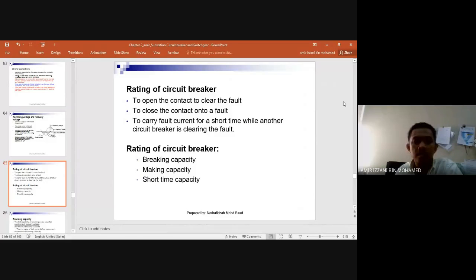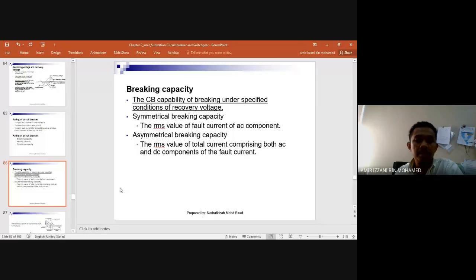Rating of circuit breaker. To open the contact to clear the fault, to close the contact onto a fault, to carry fault current for a short time while another circuit breaker is clearing the fault. So for a circuit breaker, this is the rating that we use: breaking capacity, making capacity, or short time capacity. So what is breaking capacity? It is the circuit breaker's capability of breaking under specified conditions of recovery voltage.